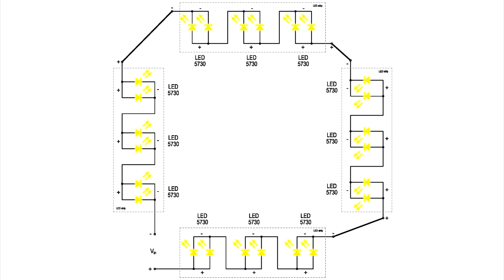Everything is working properly. Now let's see what happens when just one LED fails. Suppose this LED overheats because of inadequate cooling, a manufacturing defect, or simply normal aging. The first LED has now failed. Because these LEDs are connected in parallel, the remaining LED is now forced to carry the entire operating current. Its electrical and thermal stress increases dramatically. Very quickly, the second LED also fails. A single failed LED has disabled the entire light fixture. This is the fundamental weakness of a series-connected circuit.